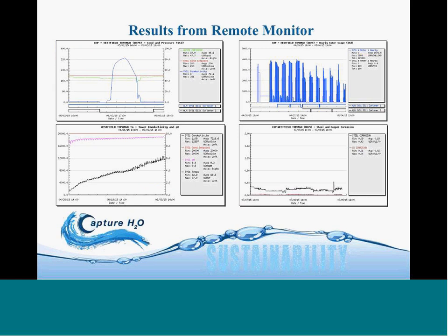So this graph shows the results of the remote monitoring. The graph on the top right shows the pre-treatment system that's treating the water. This system is online 24/7 and sends out alarms. Anyone who can access the internet and has a password can access the data. The first graph shows the water softeners that we have installed, when they regenerate and that they're getting enough salt, so they can consistently produce soft water.